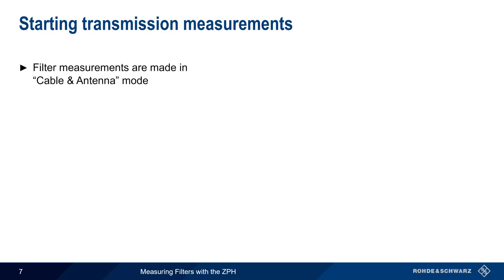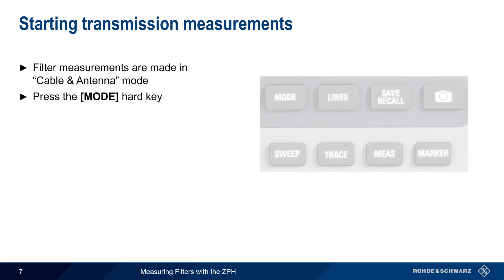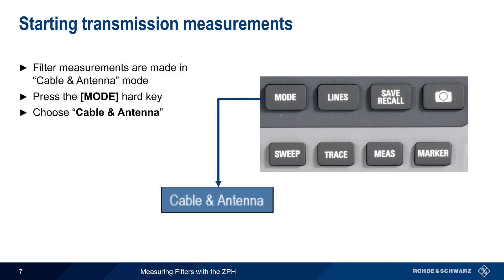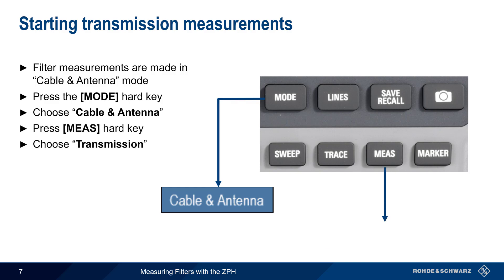On the ZPH, filter transmission measurements are made in Cable and Antenna mode. To enter this mode, press the Mode hard key on the front of the ZPH, and then choose Cable and Antenna from the list of available on-screen options. Next, press the Measure hard key and select Transmission to perform filter transmission measurements.